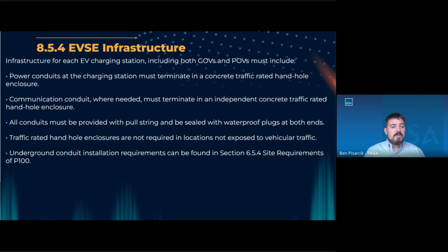So further infrastructure, including both GOVs and POVs, power conduits at the charging station must terminate in a concrete traffic-rated handhole enclosure. Communication must also terminate in a traffic-rated handhole enclosure. All conduits must be provided with pull string and be sealed with waterproof plugs. This is pretty standard for an underground conduit. Traffic-rated handhole enclosures are not required in locations that are not exposed to vehicular traffic. And underground conduit installation requirements can be found in 6.5.4. That's back up in Chapter 6 in the site requirements. There are additional requirements there for conduit installation underground.